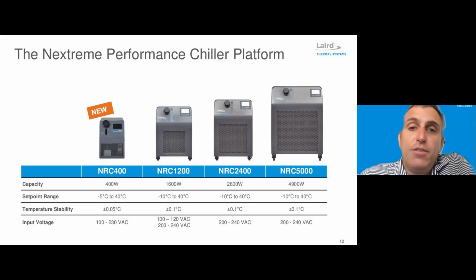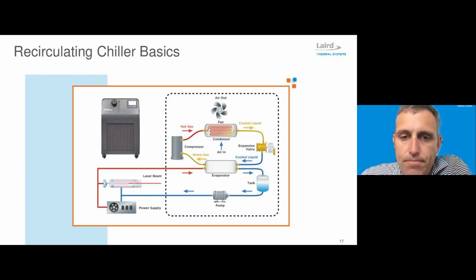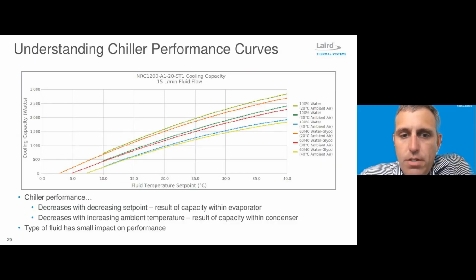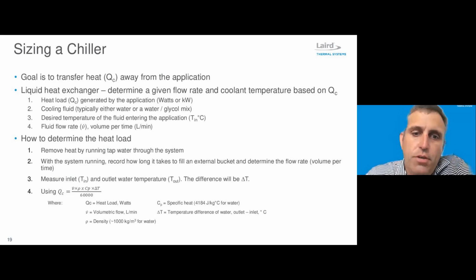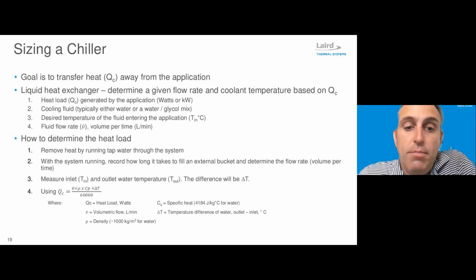So that may not make sense on the surface, but what tends to happen in applications is that equipment manufacturers are trying to maintain a certain temperature rise across their product. So with higher heat inputs, in order to keep that temperature rise constant, they increase the flow rate. So in the example I had given, we'll go to this slide just to provide the visual. In this equation that's shown here in bullet 4 on the bottom, heat load is proportional to the mass flow rate times the temperature rise.